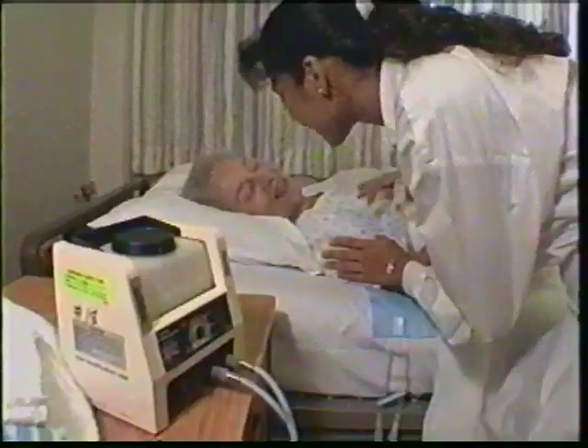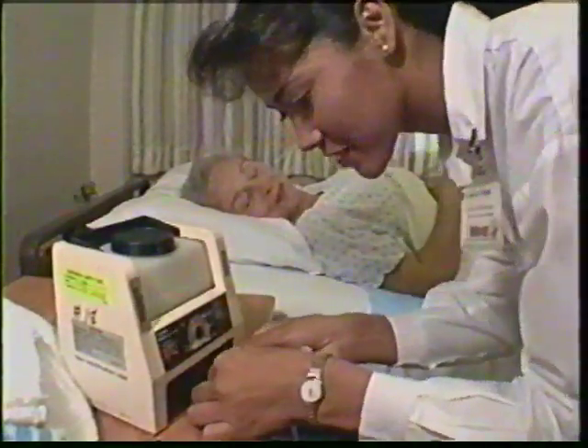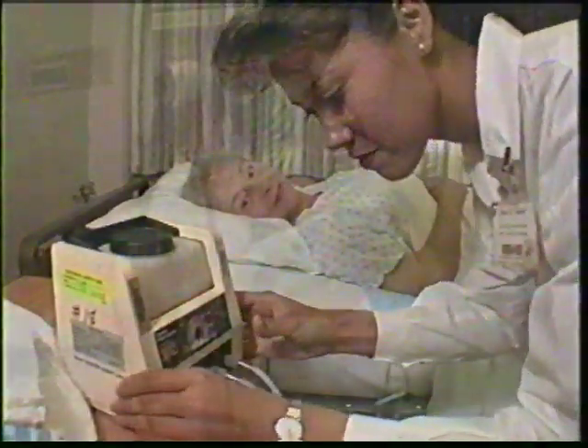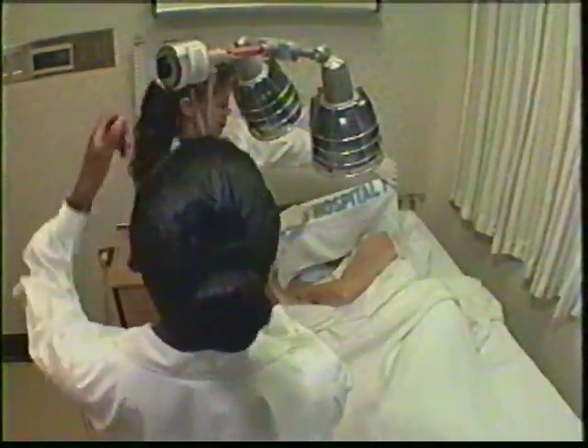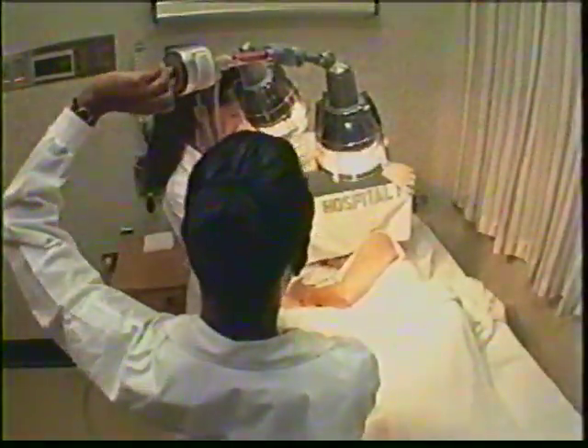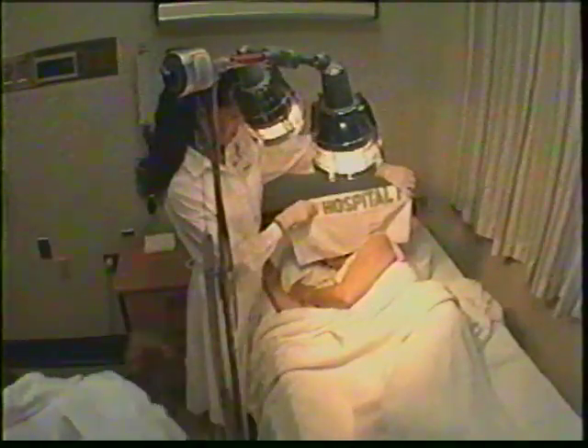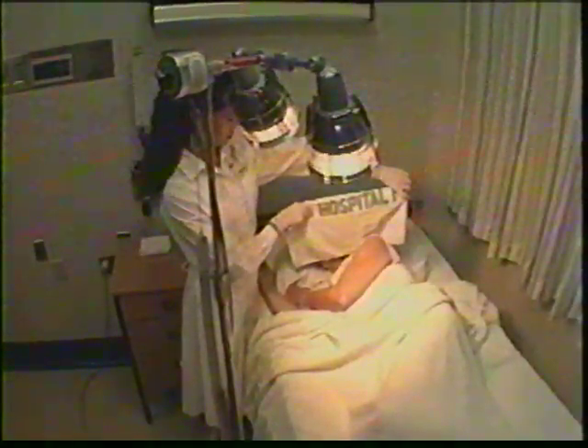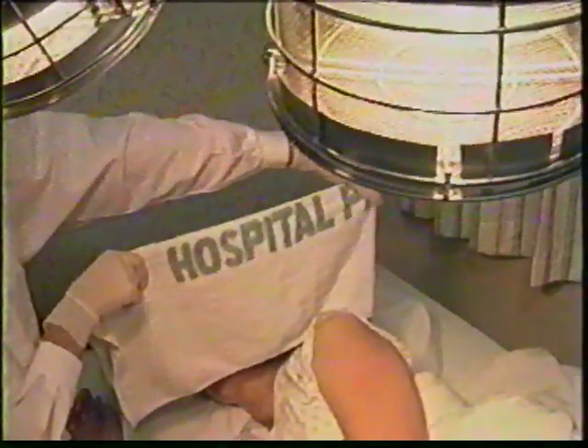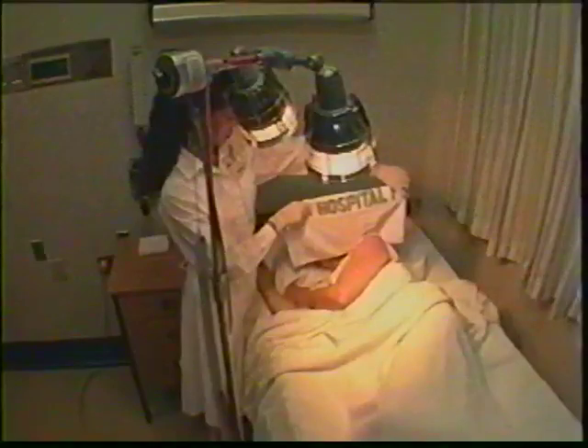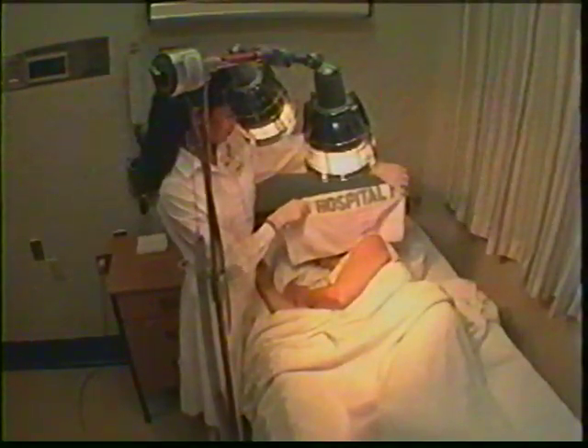Here are some tips. Check soundness of heating pads, hot water bottles, and other electrical appliances before use. Keep infrared lamps and light cradles at least 18 inches from the patient's body. Use no more than a 25-watt bulb in a light cradle. If the site to be treated is near the head, protect the patient's eyes with a towel or washcloth. Make sure that a staff member attends the patient the entire time the equipment is in use.